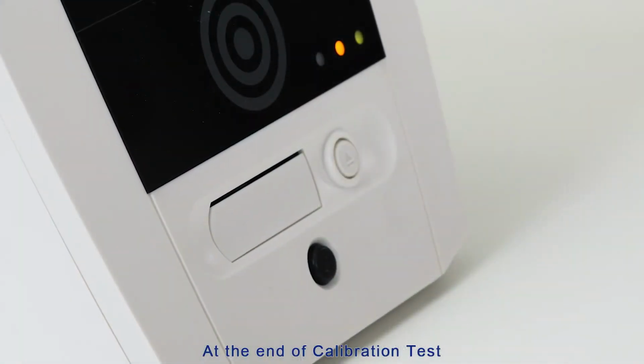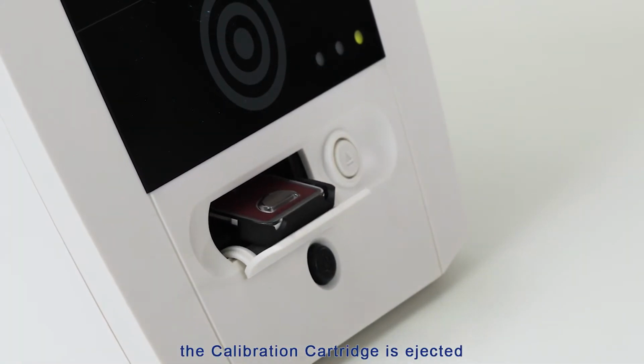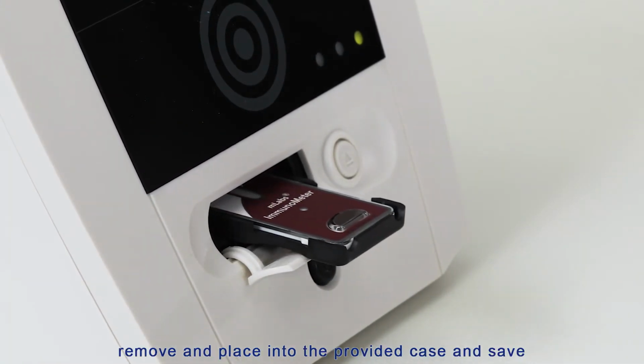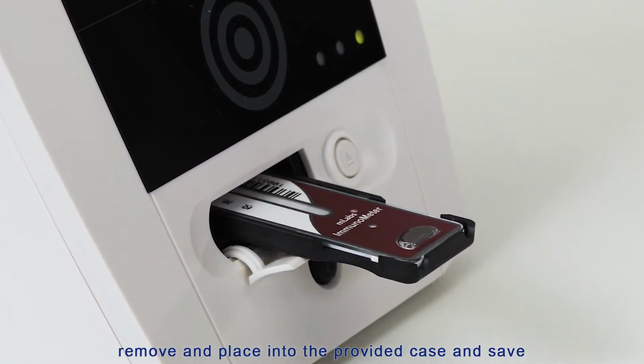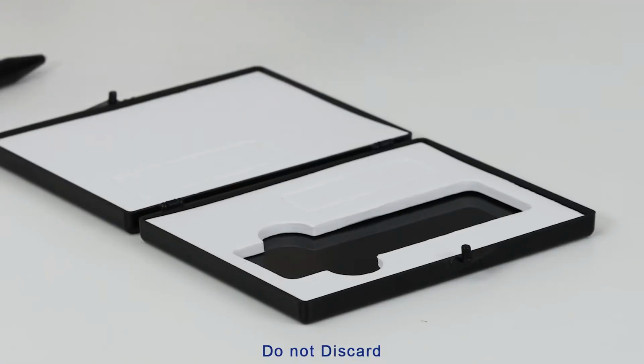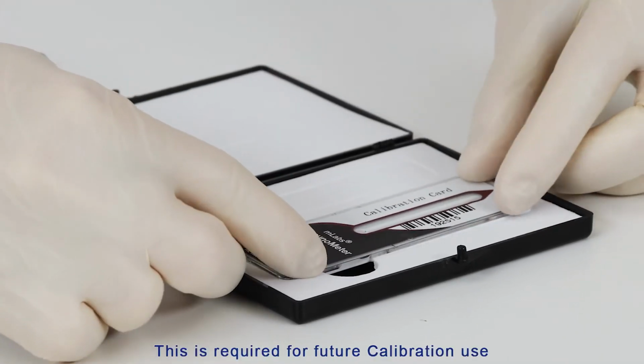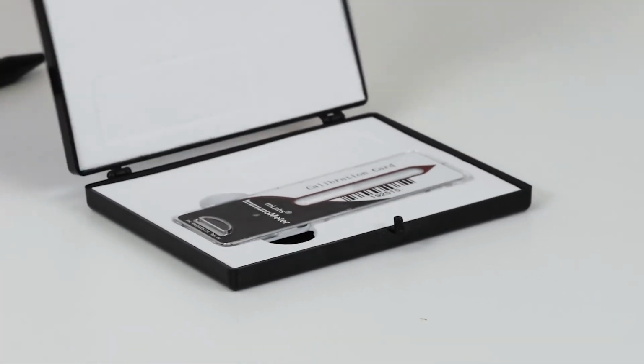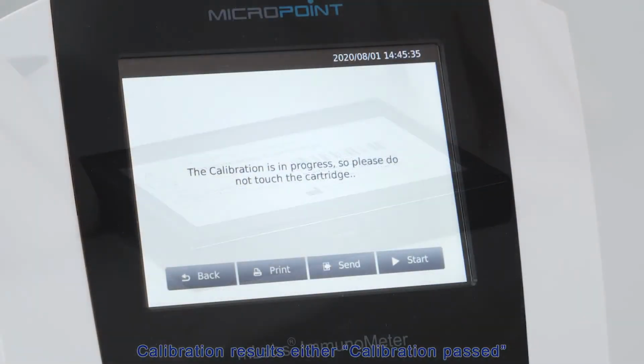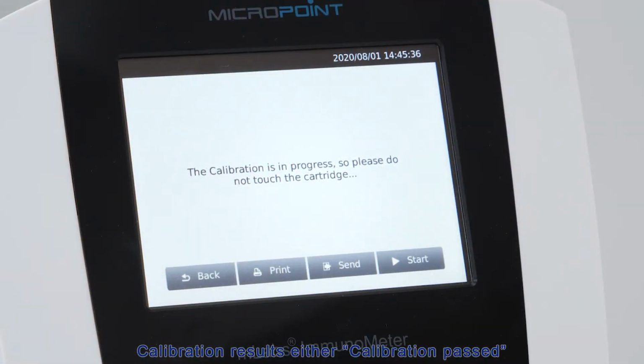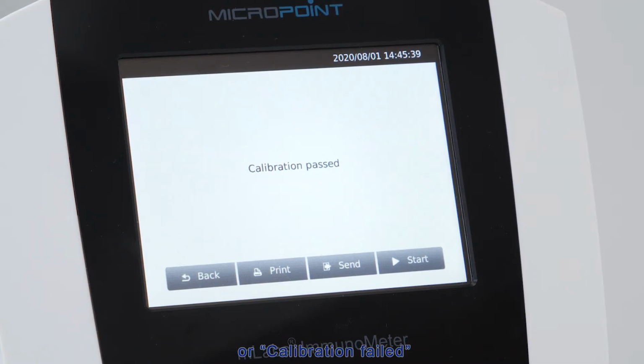At the end of calibration test, the calibration cartridge is ejected. Remove and place into the provided case and save. Do not discard. This is required for future calibration use. Calibration results are either calibration passed or calibration failed. If calibration failed, retry the calibration with correct steps. If failed again, please contact your Micropoint distributor for further information.